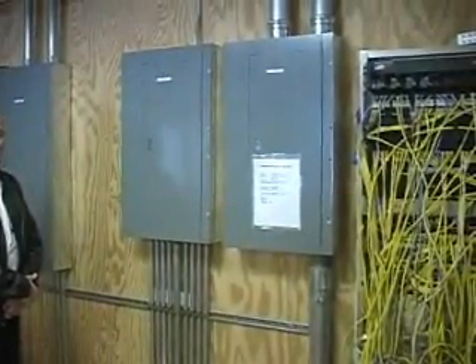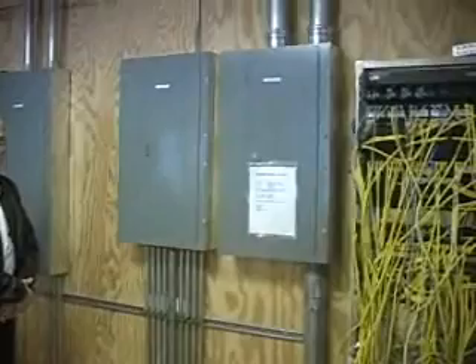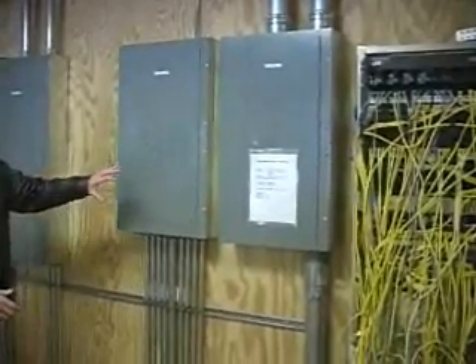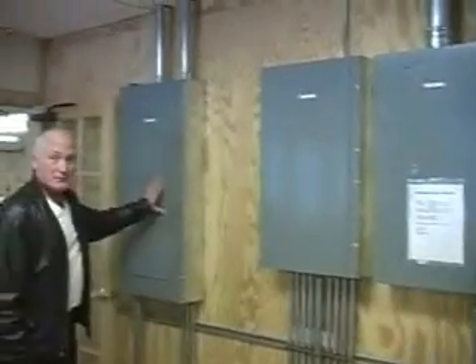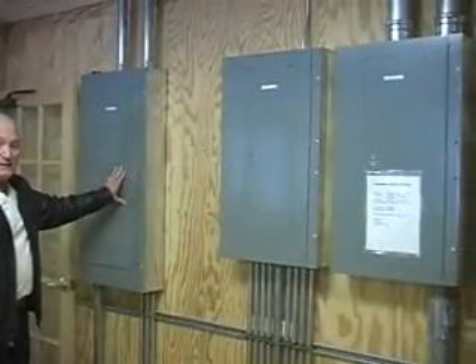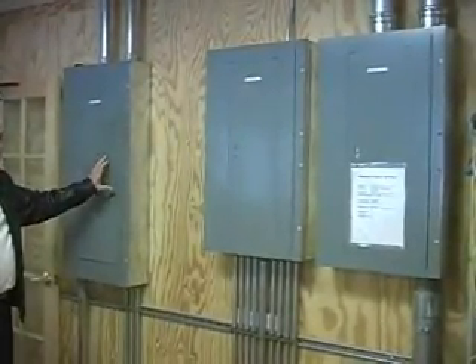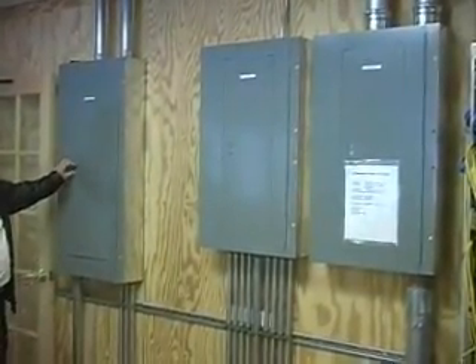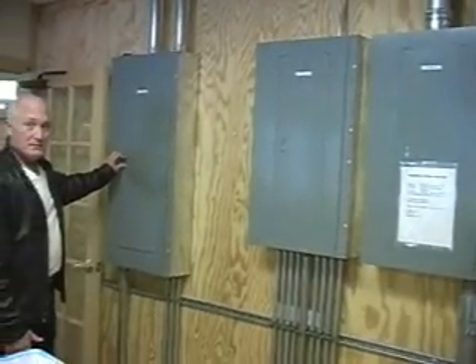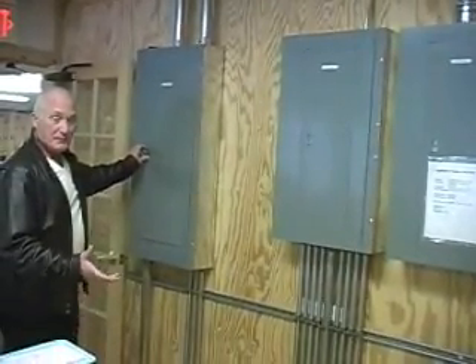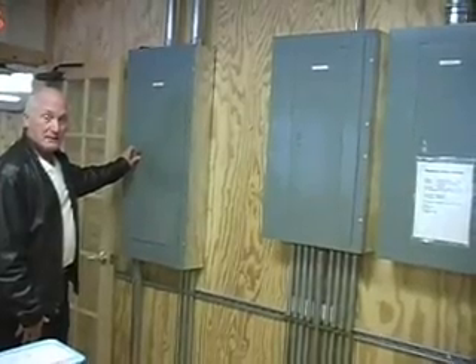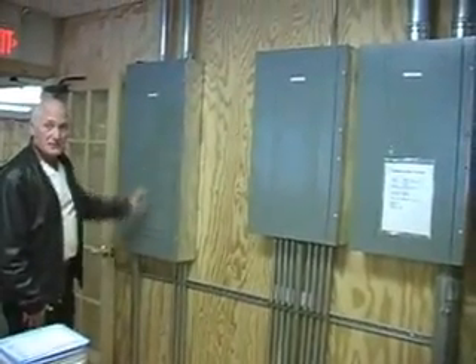Plan to be around forever. You have to plan for the day that you need to modify or make some changes. Therefore, every single floor of this building has its own electrical panel system, so that if a modification was needed, it simply has to be done from these panels forward. You don't have to go back and do the entire building. For example, we could remodel 2,000 or 3,000 square feet, and it would only be a matter of touching one panel.